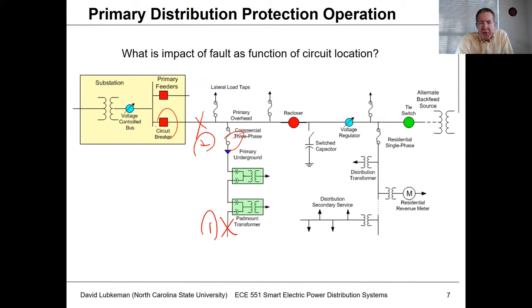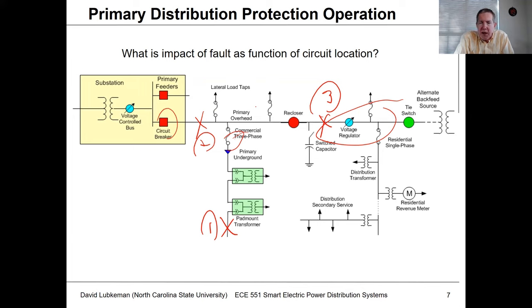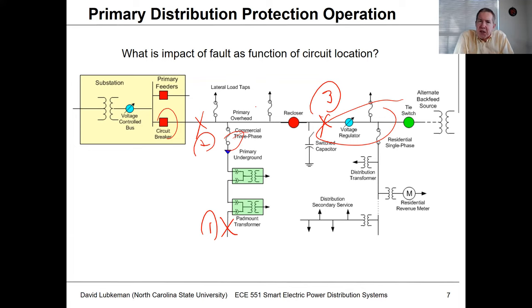If we had an event right here, what would happen is the recloser would operate hopefully before the circuit breaker. Then we would lose all these customers out here, but the customers upstream of the recloser would be okay. What you need to know for reliability analysis is all the different possible fault locations — sometimes referred to as contingency events — and how the protection is going to operate for each of those different fault locations, because that tells us what we expect to see given certain failure rates of components.